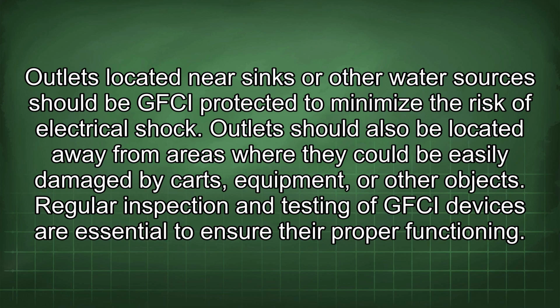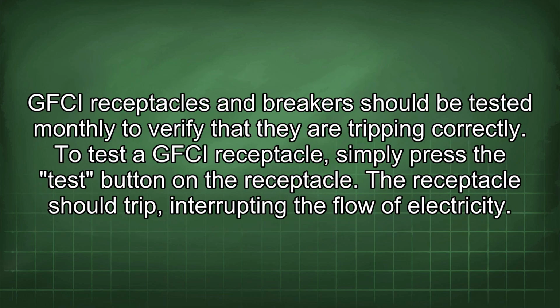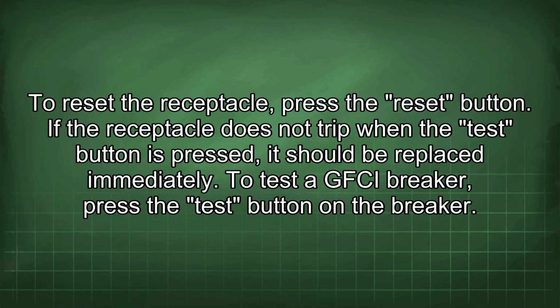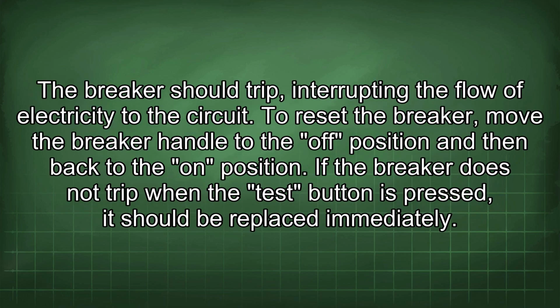Regular inspection and testing of GFCI devices are essential to ensure their proper functioning. GFCI receptacles and breakers should be tested monthly to verify that they are tripping correctly. To test a GFCI receptacle, simply press the test button on the receptacle. The receptacle should trip, interrupting the flow of electricity. To reset the receptacle, press the reset button. If the receptacle does not trip when the test button is pressed, it should be replaced immediately. To test a GFCI breaker, press the test button on the breaker. The breaker should trip, interrupting the flow of electricity to the circuit.